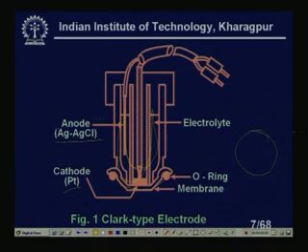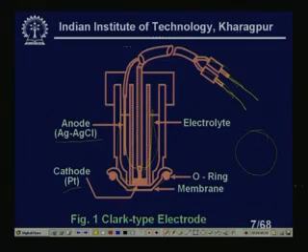This is the two-probe output, two wires coming out, which are to be connected. You can see here two wires are coming out, through which I will show the circuit for how we will measure that current, right. So, this is our basic Clark type electrode.